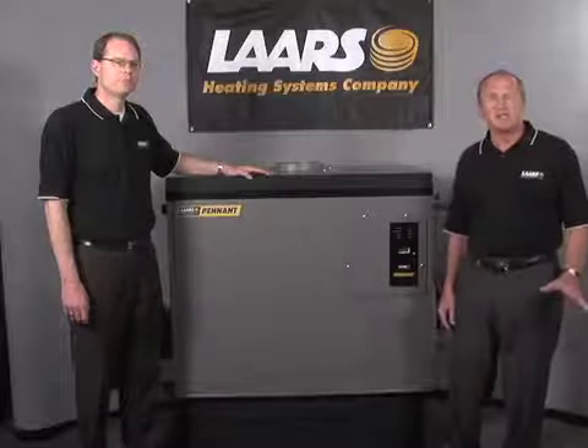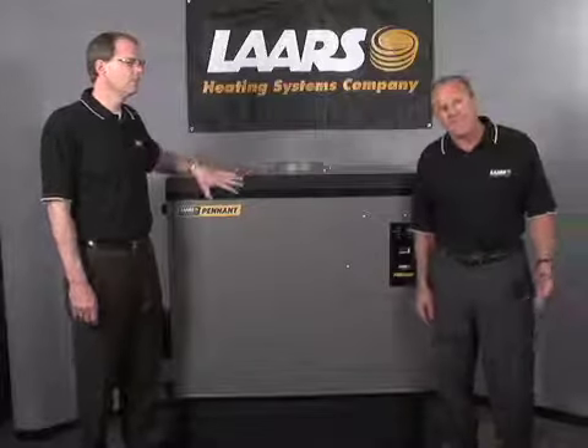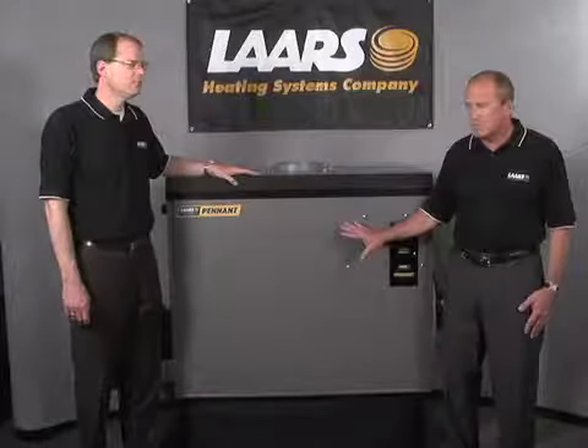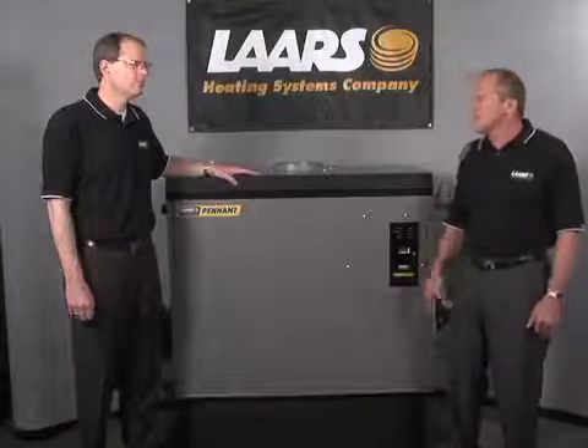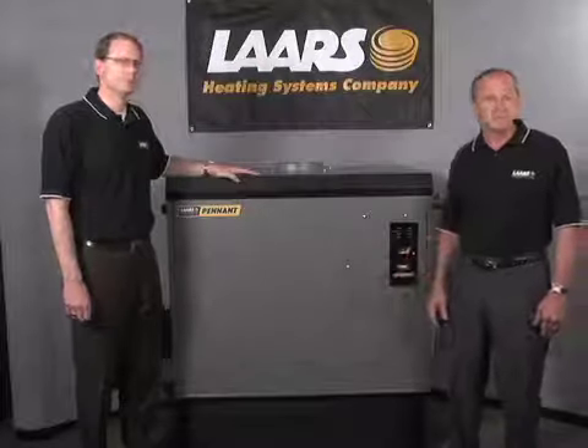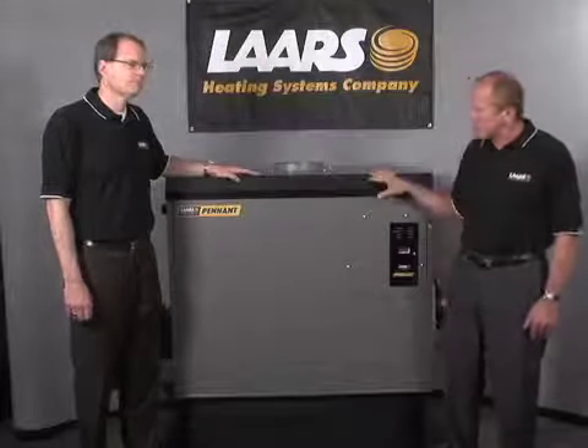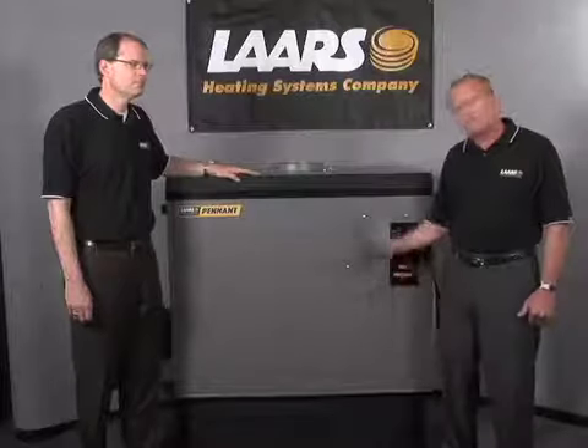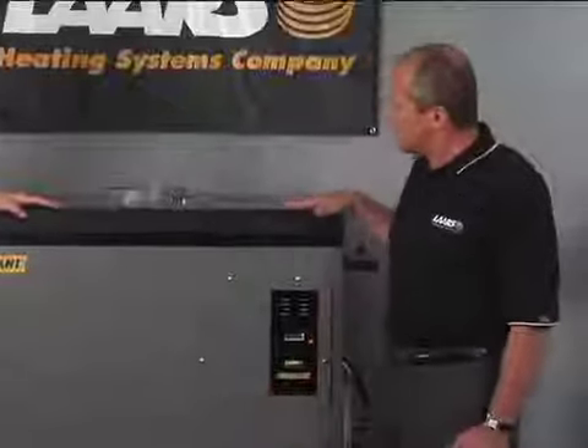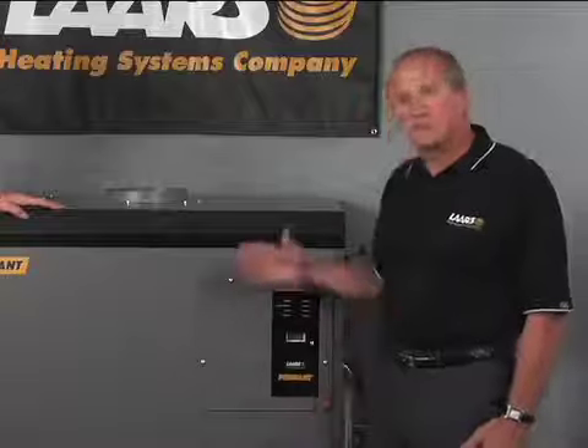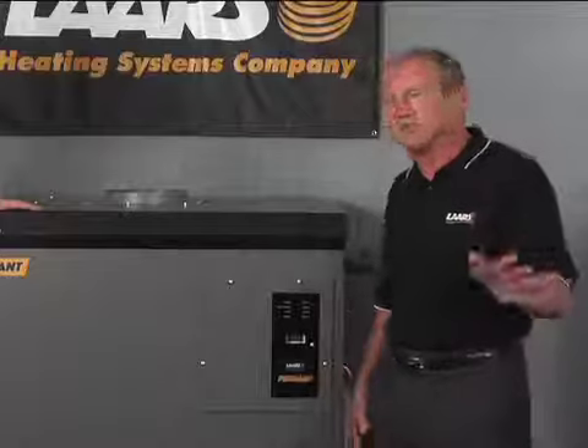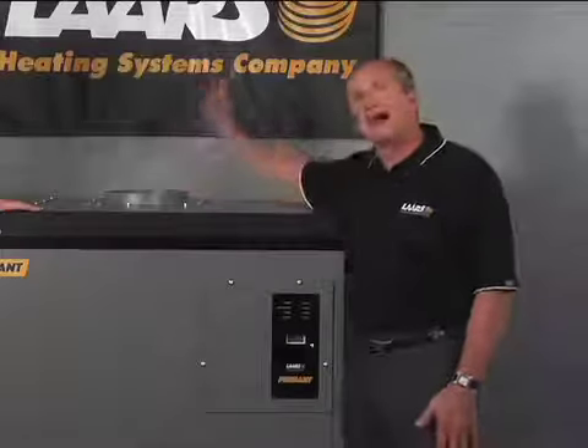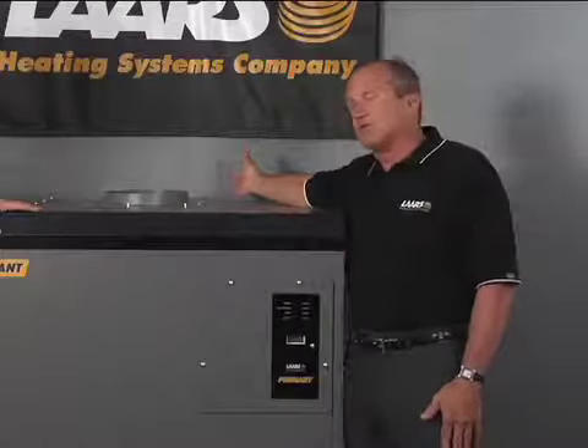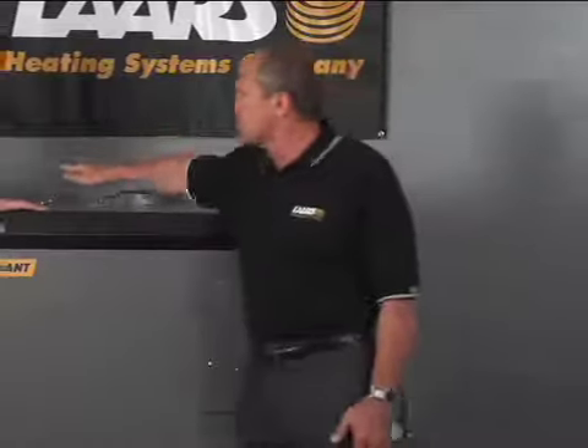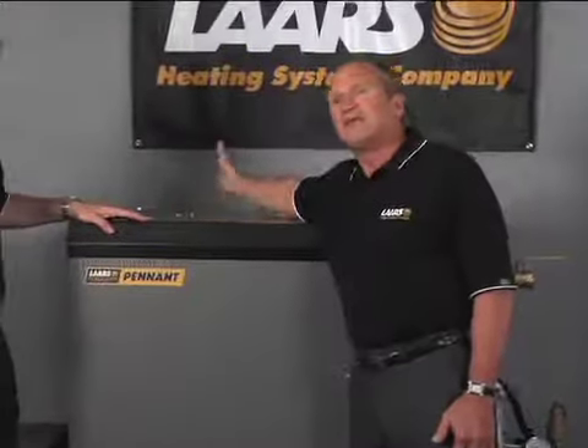From a venting standpoint, if you're used to installing non-fan assisted appliances, which this one is a fan assisted appliance, your vent size is going to be decreased significantly. This product here is up off the ground for our video, but you can set this on the ground, and actually you can rack these and stack another unit right on top, because you have the ability to vent this product either from the top and/or from the back.